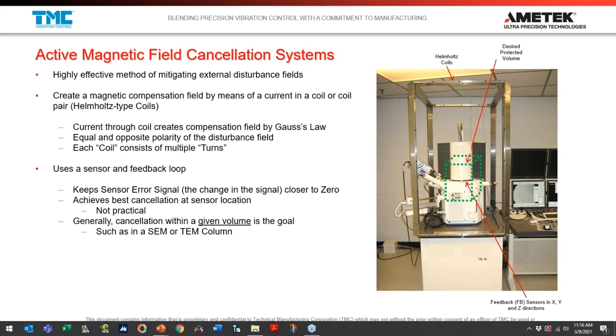The goal of the feedback loop is to keep the sensor at zero. The sensor senses the disturbance field and sends a signal to the controller, which sends a current to the coils. That current is of opposite polarity and equal magnitude to what's being sensed at the sensor, so you come to a stabilization where the sensor stays as close as possible to zero.